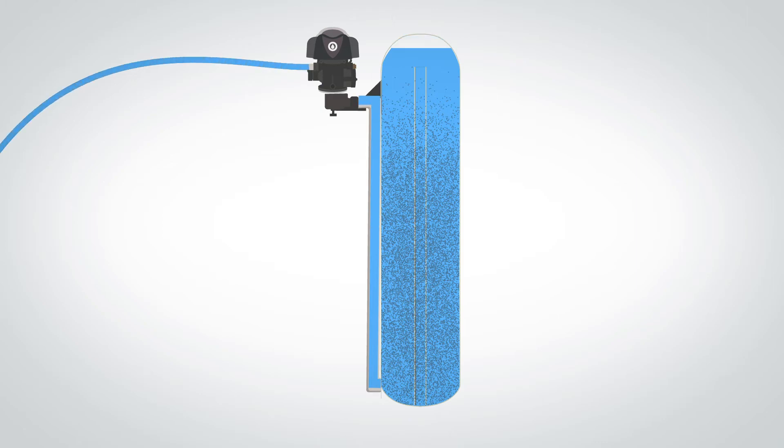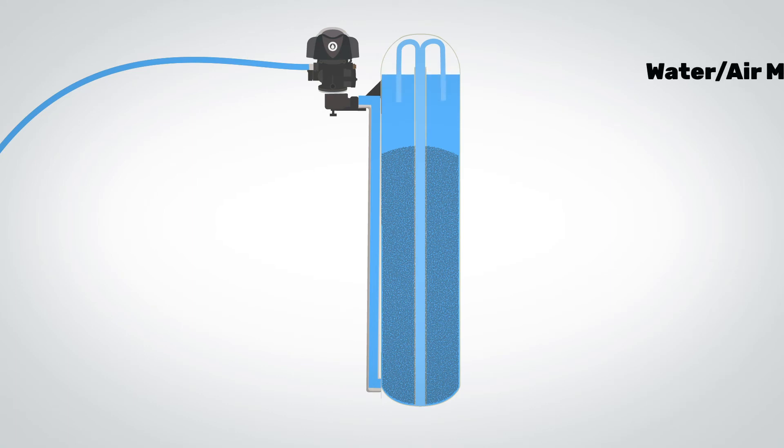After the backwash comes the air replenish step. During this step, water is driven through an air injection assembly, which creates suction to pull in fresh air, similarly to how a softener draws in brine. This mixture of air and water is directed up the riser tube and down through the media bed, replenishing the pocket of air at the top of the tank.